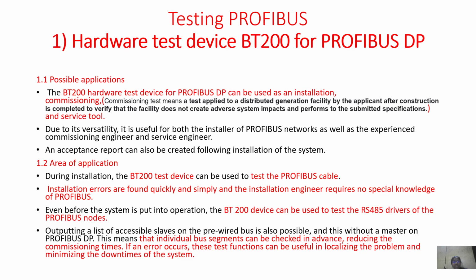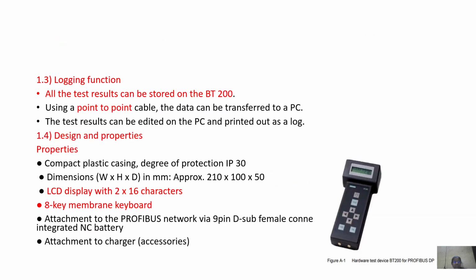So installation errors are found quickly using Profibus. It is used to test the RS485 drivers of the Profibus nodes. So individual bus segments can be checked. So these are other areas of application. Logging function: all the test results can be stored on the BT200 using a point-to-point cable. The data can be transferred to a PC. The test results can be edited on the PC and printed out as a log.